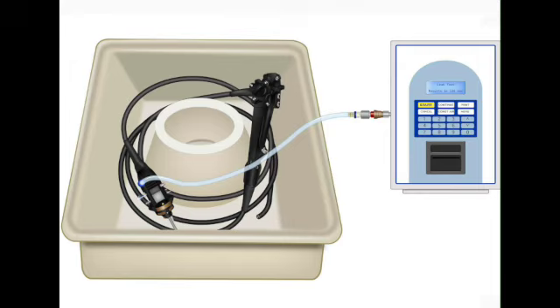Okay, so the test runs, you've done all the movements, now you're waiting for the result. Pass or fail? Right. If you get a pass, great, fantastic news. That scope is sound. It moves on to the next stage, which is manual cleaning. Simple enough, but what if it says fail? Okay, fail means you stop. Everything stops. You cannot proceed to cleaning.